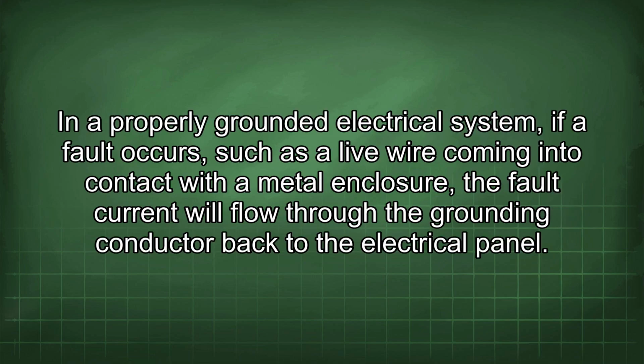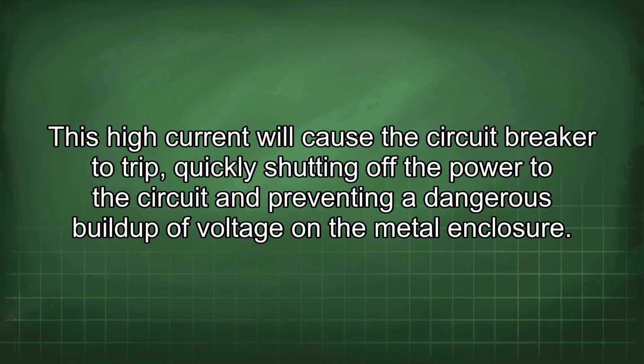In a properly grounded electrical system, if a fault occurs, such as a live wire coming into contact with a metal enclosure, the fault current will flow through the grounding conductor back to the electrical panel. This high current will cause the circuit breaker to trip, quickly shutting off the power to the circuit and preventing a dangerous buildup of voltage in the metal enclosure.